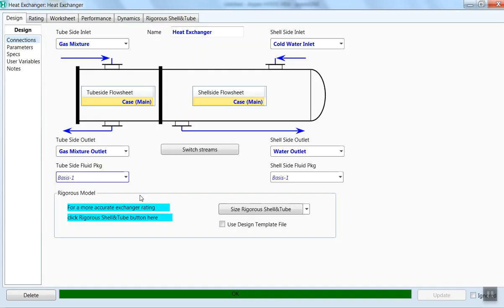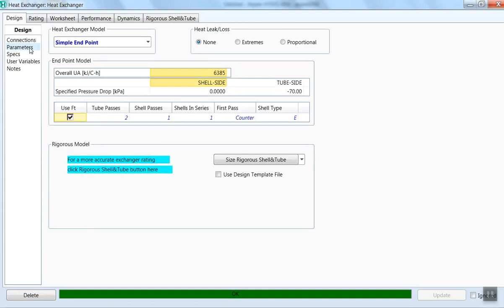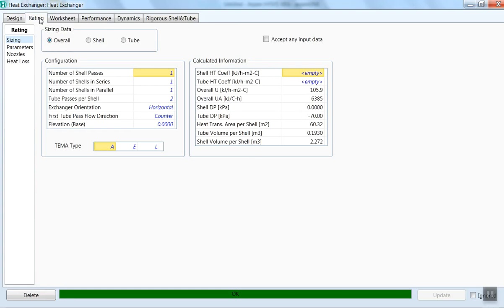If you click on Design, this is our heat exchanger. Under Parameters, the overall heat transfer coefficient is 6385, tube passes used is 2, and shell passes is 1. Under the Rating tab, shell side pressure drop is considered zero, tube side is minus 70 kPa. Tube volume is 0.193 m³ and shell volume per shell is 2.272 m³.